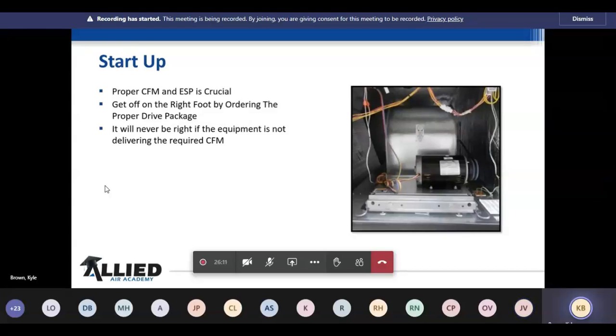But this picture right here also shows a lot of the inspection. If you look at the wiring, this picture was sent to me because I had some damage on the back side of this coil right here, and it was corrected. It was kind of finned down. Everything looks okay now. But my question to the DSR was, okay, these wires right here, did they come from the factory like this, or did someone cut the wire ties loose? The reason I asked is that in this particular unit, both your suction and your liquid line run along the top of the unit right here, and these should be wire tied to that suction line. If it's a heat pump, it's going to be the vapor line, but it'll still be insulated, so we don't worry about the wires shorting out like I showed you on the discharge line.